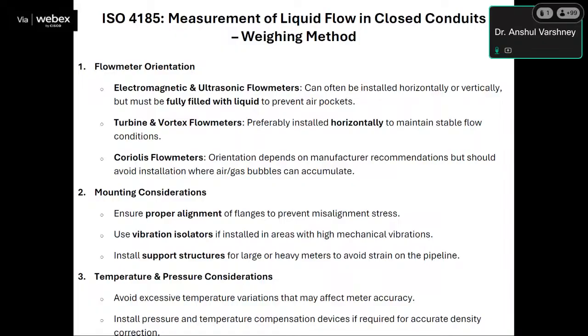However, turbine and vortex flow meters are preferably installed horizontally to maintain stable flow conditions. For Coriolis mass flow meters, orientation depends on the manufacturer's recommendation, but installation where air or gas bubbles can accumulate should be avoided. There should not be any air or gas bubbles in the U-tubes. Mounting considerations: ISO 4185 states that one should ensure proper alignment of flanges to prevent misalignment stress. Use vibration isolators if installed in areas with high mechanical vibrations. Install support structures for large or heavy meters to avoid strain on the pipeline.